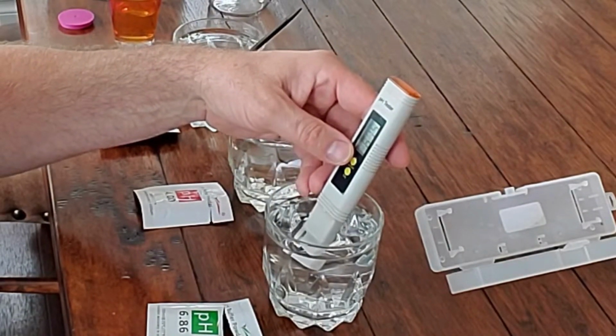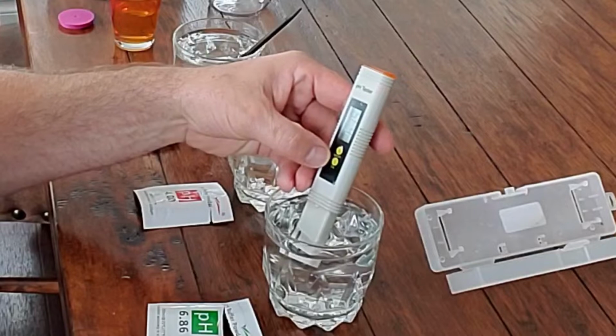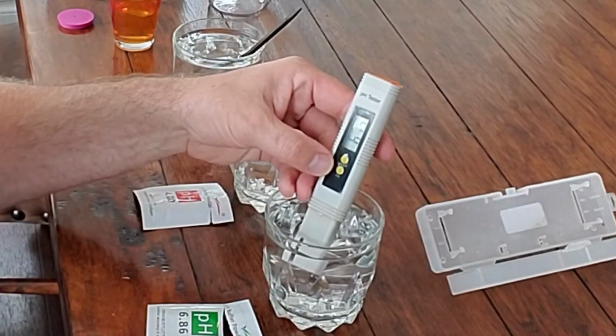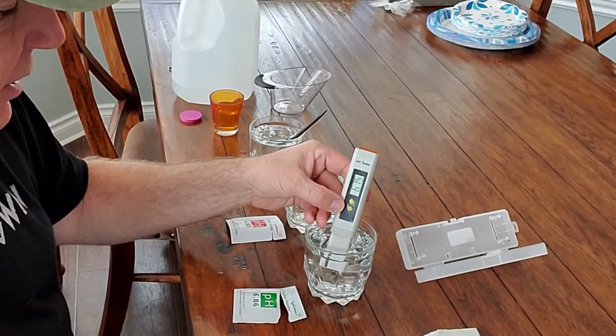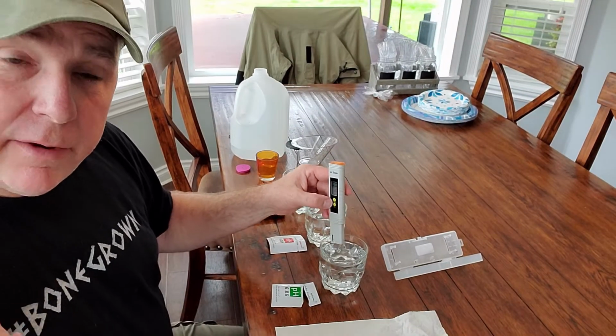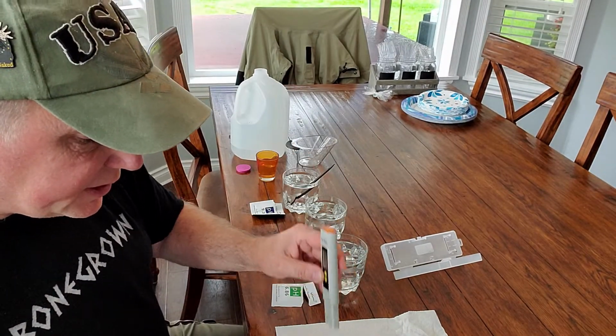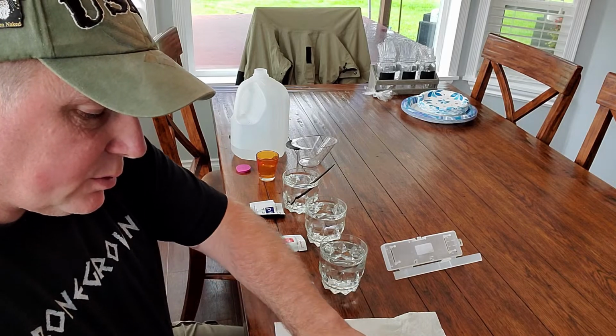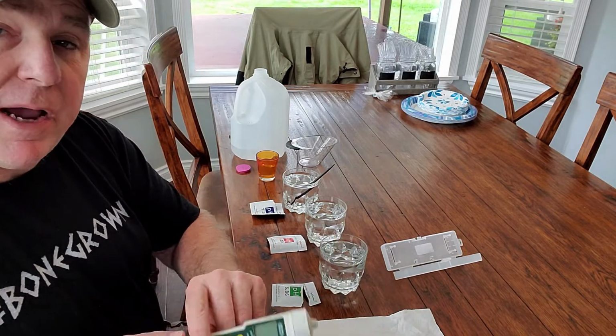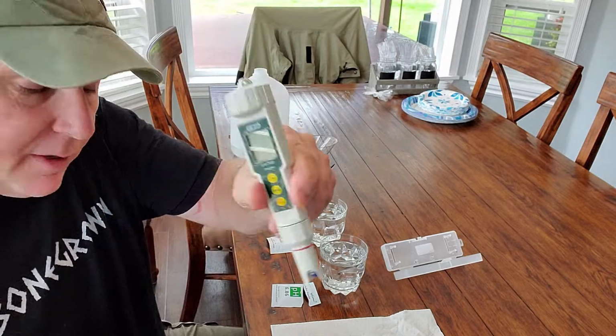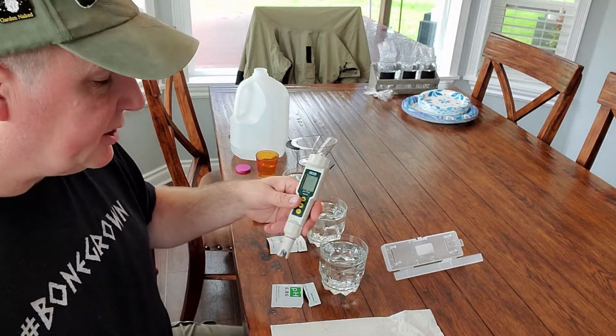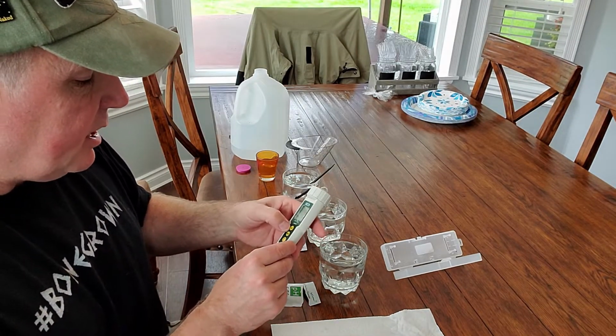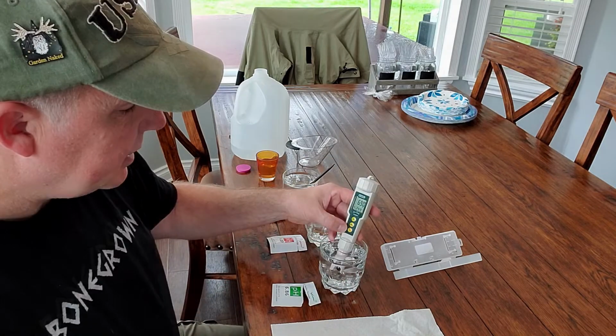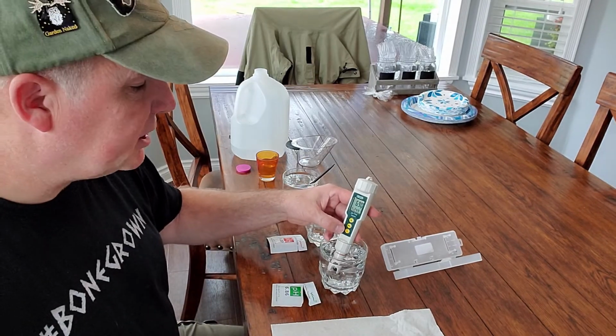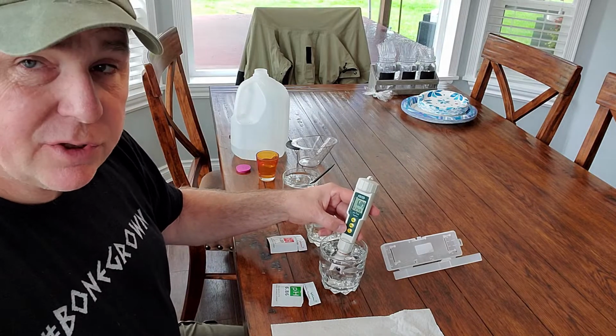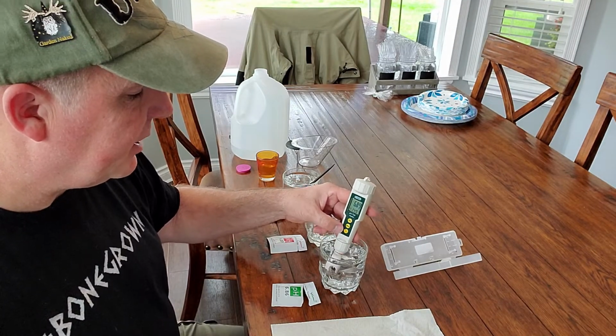And it looks like my reading is a little low. It's at 6.75, as you can see here. Now, to do a sanity check, I'm going to take my newly calibrated meter and test this just to see that it comes out at my normal levels. I know that this one calibrated to 6.86, and that's what I'm looking for it to show up at.